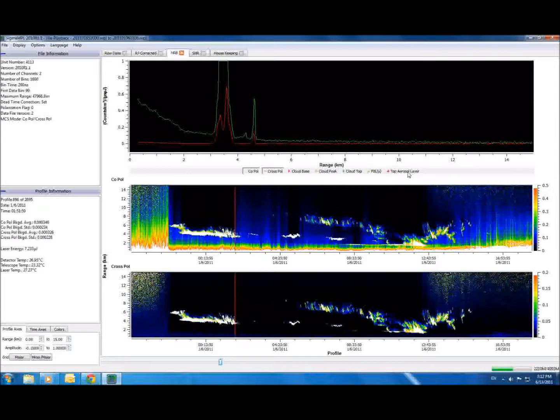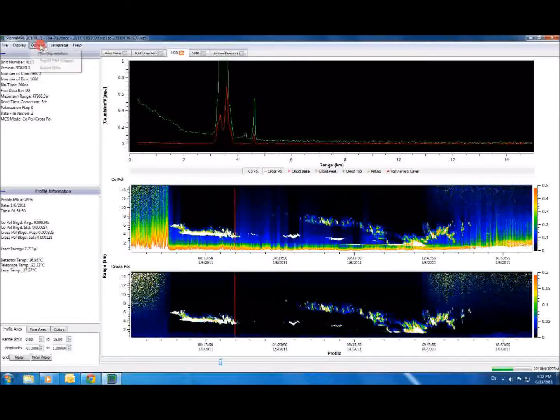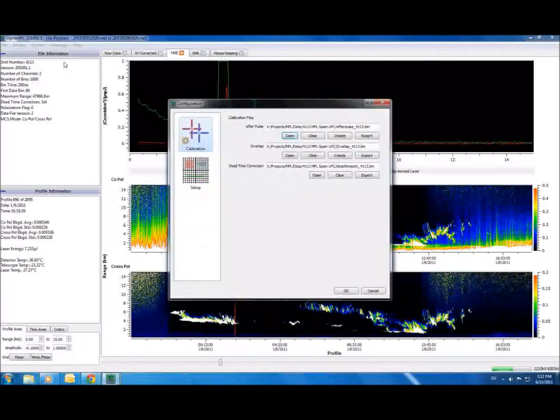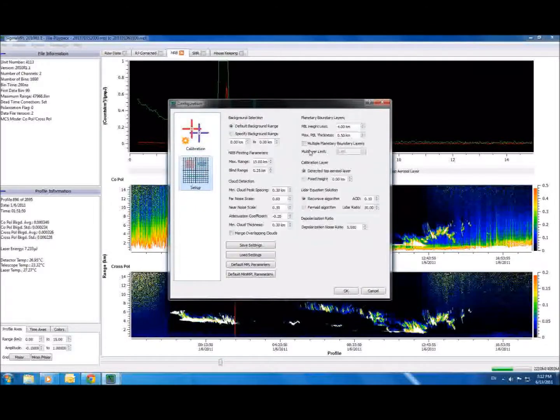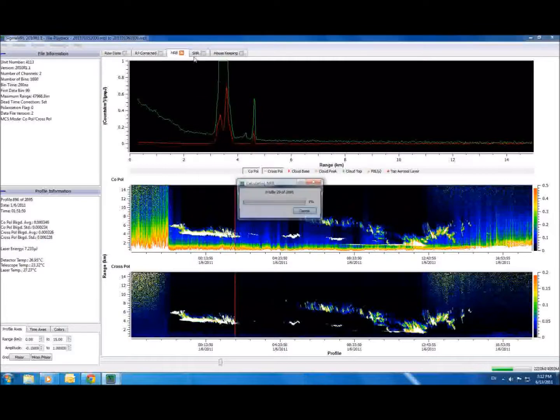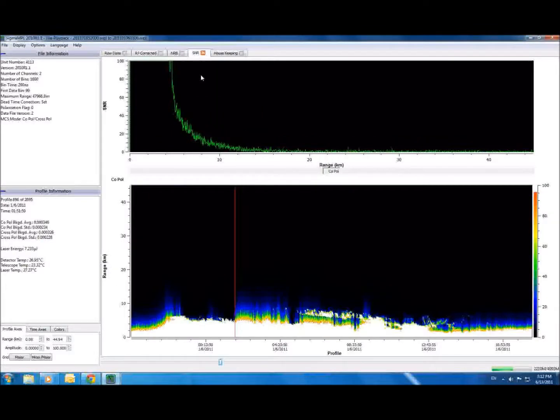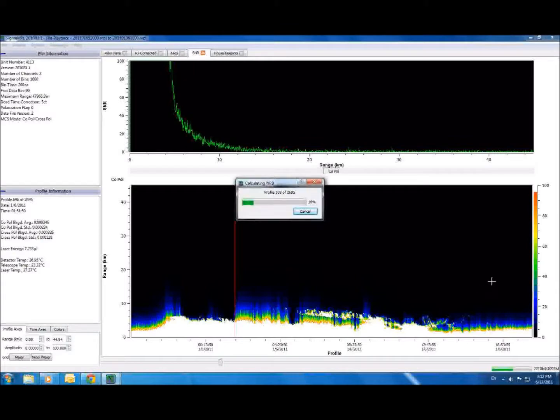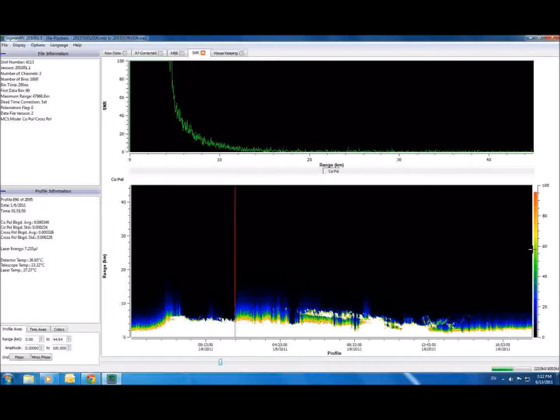The theories and equations used for these calculations can be tweaked in the calibration window here. Sigma MPL now also comes with an SNR, or signal-to-noise ratio tab. Here, scientists and researchers can quantify the quality of the data they are using and monitor the effects that outside noise is having on the instrument.